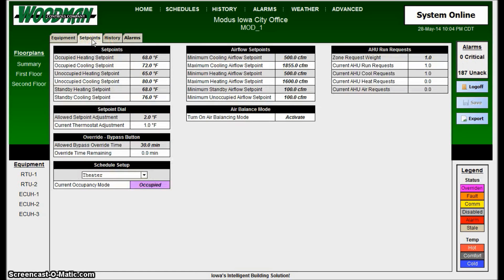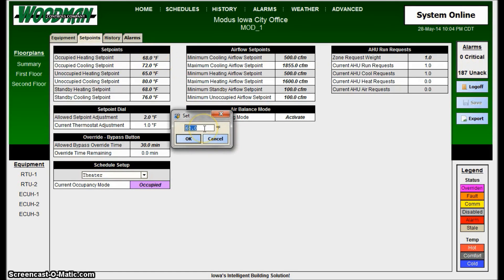On the set points page, these are not overrideable points. This is just where you're setting up the normal operational parameters of the system — so as it goes occupied and unoccupied, these points are what the program will follow. They're not overrideable; they're just settable. For example, for the occupied heating set point, you click and it pops up — you can see there are no override timers. This is just setting up normal operation.